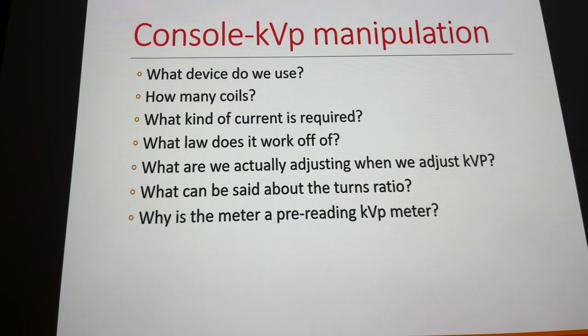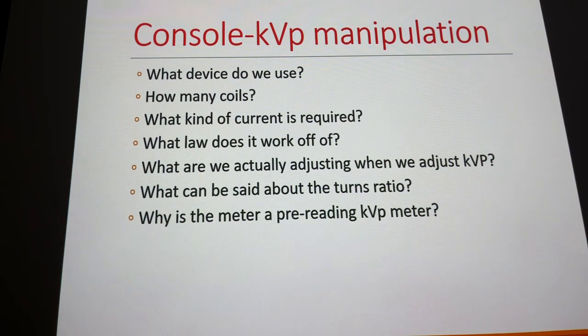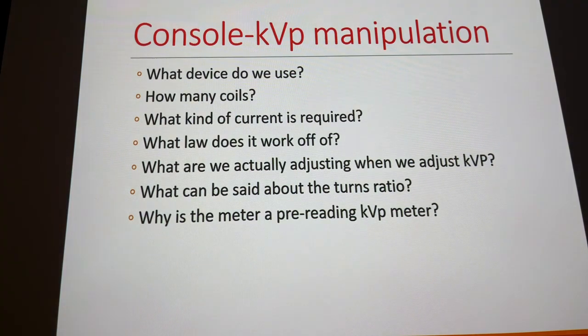The voltage change is directly related to the change in turns ratio between the primary and secondary sides. If we increase the number of turns on the secondary side, voltage goes up; if we decrease them, voltage goes down. So when we adjust KVP, we're adjusting the contacts on the secondary side of the auto transformer. The turns ratio is variable — we can increase or decrease it.